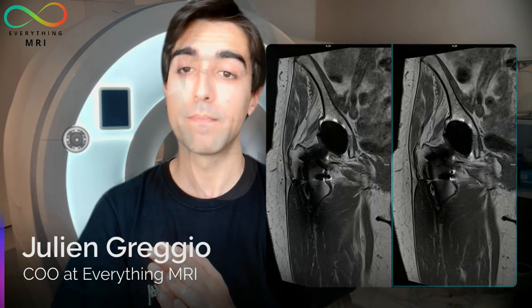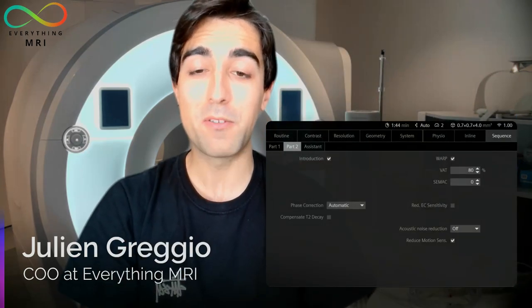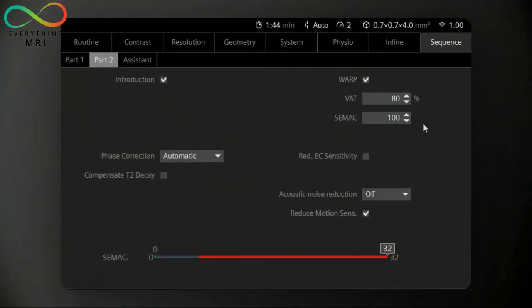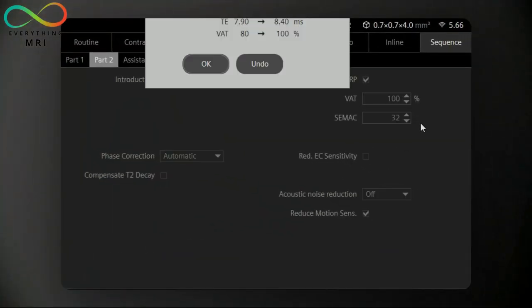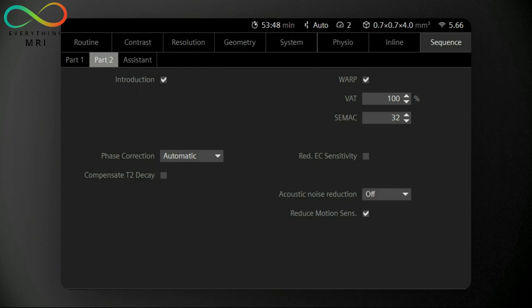It must also be said that VAT has the major limitation of focusing on the reduction of in-plane distortions only. To reduce through-plane distortion instead, we need to rely on SEMAC. Similarly to VAT, SEMAC applies a number of additional encoding steps to correct the distortion caused by metal implants. However, these are meant to significantly reduce also those artifacts that VAT is usually not able to rectify.